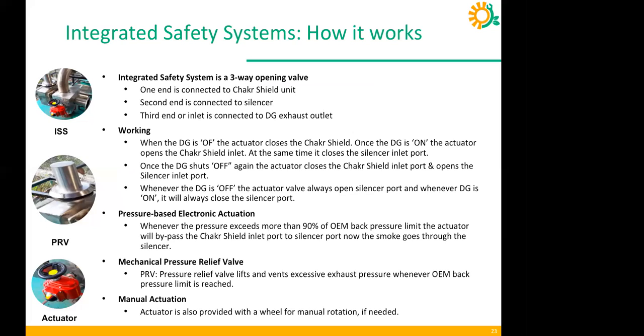If I give you a range, my device will be working between 2 to 4 kPa, 2 being the lowest, 4 being the highest, depending upon the load that you give to the DG and the capacity of the DG. But in any worst case scenario, if back pressure starts to build and is about to reach 6.5 kPa, then we have safety systems installed, and even before it reaches 7 kPa, our safety system will work and will ensure that nothing wrong happens to the DG.